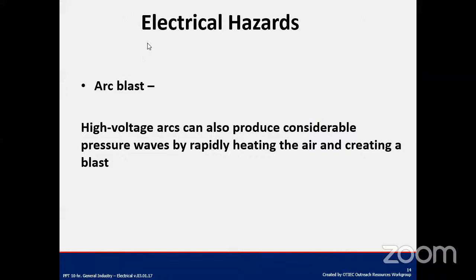Arc blast - somebody was asking whether it is arc blast or arc burst. It is arc blast. High voltage arcs can also produce considerable amounts of pressure waves by rapidly heating the air and creating a blast. Just imagine 35,000 degrees Fahrenheit of temperature rapidly interacting with the air - that in turn produces a huge amount of pressure waves.